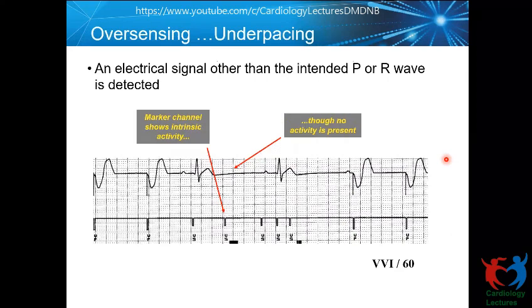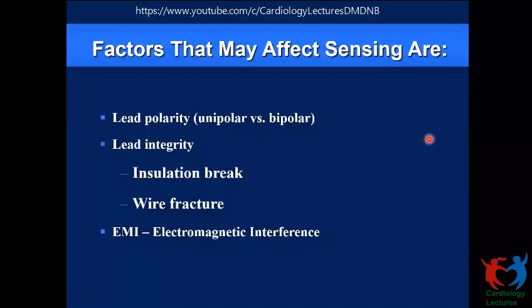It's oversensing something when there is no waveform corresponding to that. This might represent an electromagnetic interference. This might also represent a lead-related problem. When there is a lead fracture or an insulation break, there could be oversensing that can reset the pacing cycle. So we will see that in greater detail. Both insulation break and a wire fracture can affect the sensing characteristics adversely, and your polarity, whether the setting is unipolar or bipolar in configuration, can also affect the sensitivity.